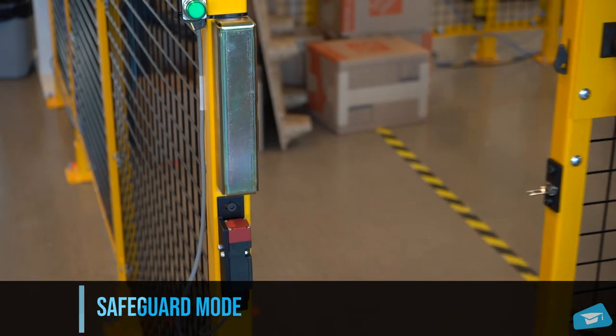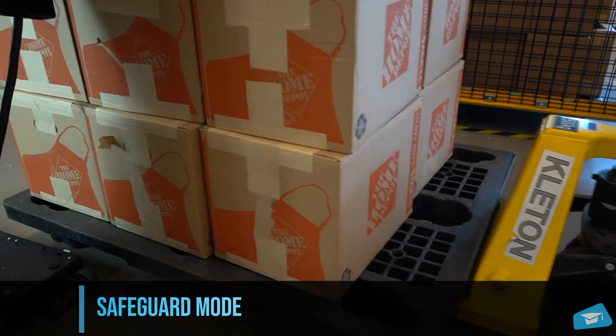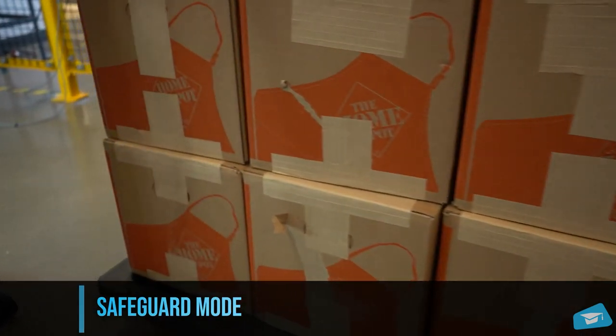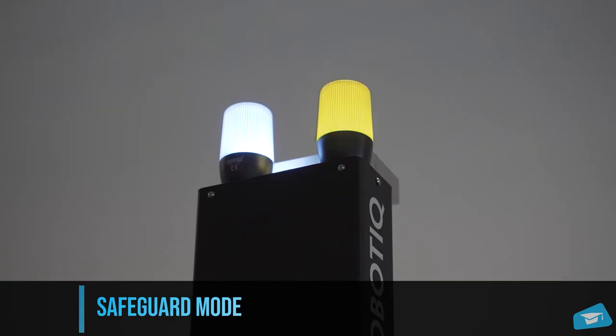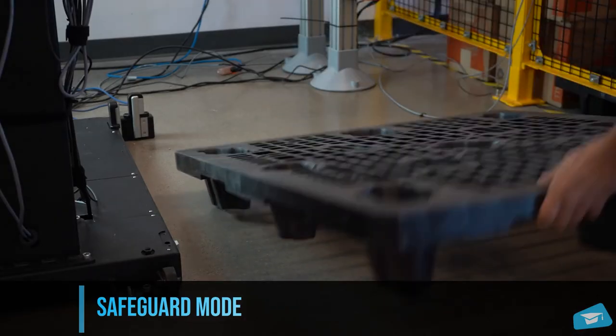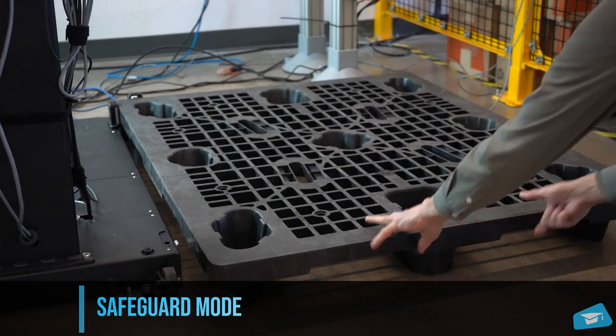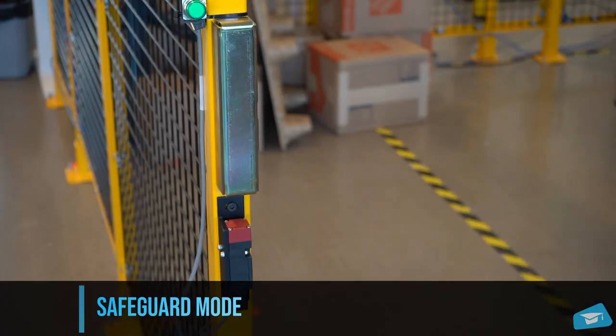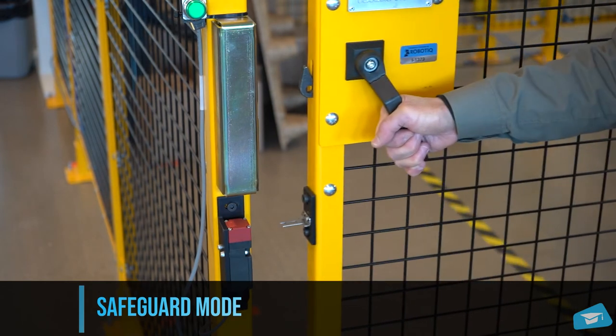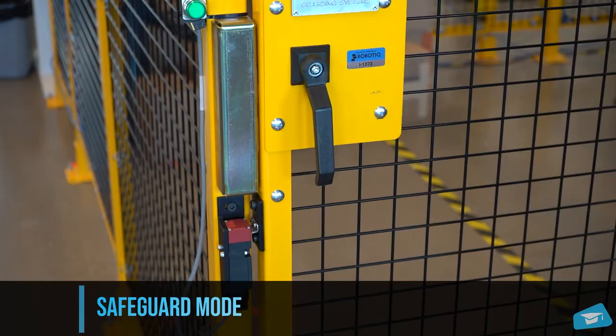The cell should enter a safeguard stop to protect the operator, and the indicator light will be yellow. At this point, the operator needs to tend the cell, get a filled pallet and place a new pallet. Note that while no pallet is present, the indicator light will be yellow. Once the operator exits the cell, it resumes in normal operation mode.